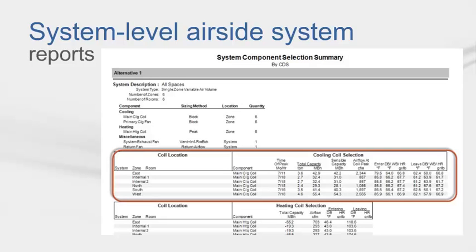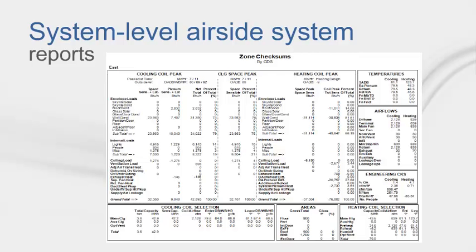After you have completed the rest of the model and finished calculating, you will want to look at the System Component Selection Report for all coil and fan sizing information. Note that we do not do coil selection in this program — we give you the tonnage and the entering and leaving temperatures. You can refer to the zone checksums or room checksums for VAV box sizing information, and the system checksums for supply fan, preheat coil, and main cooling coil sizing information. Note that some peak numbers, like air flows in your zone checksums, will not add up to what is shown in the system checksums, because the system checksums show the peak at one given time, not just the added-up values of all zone peaks.